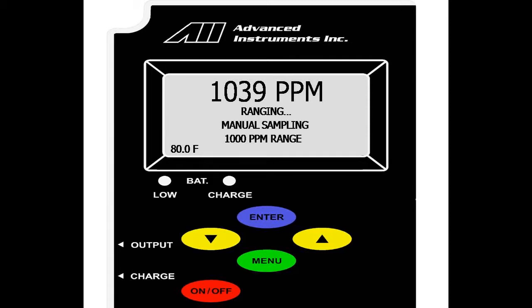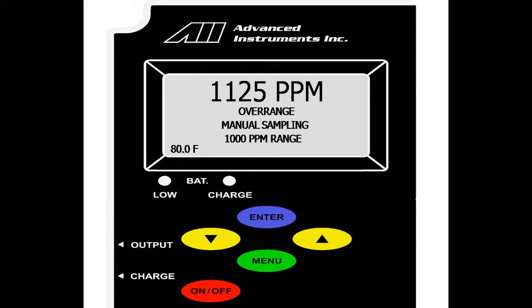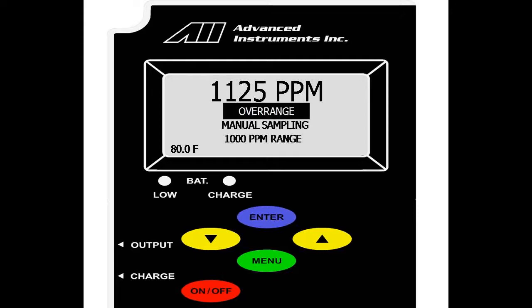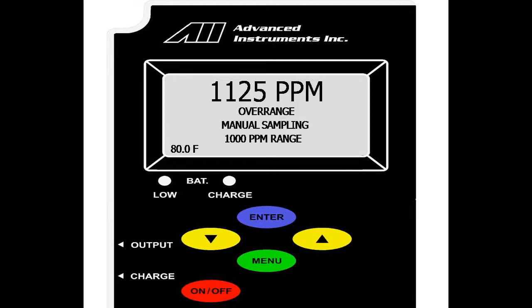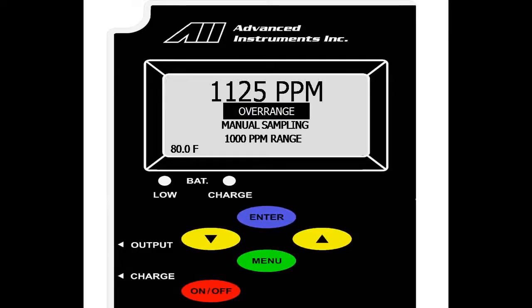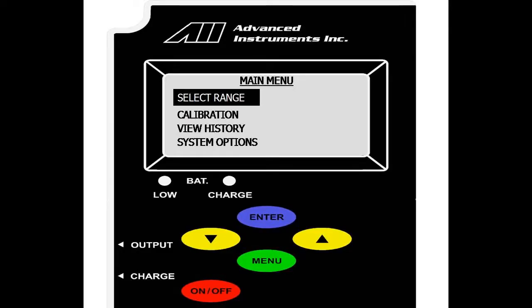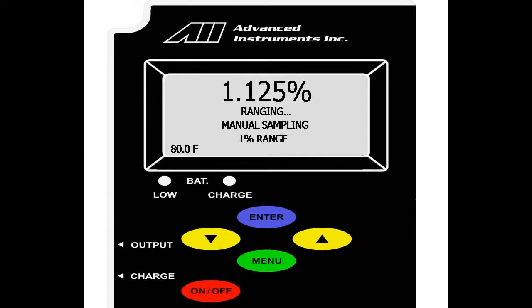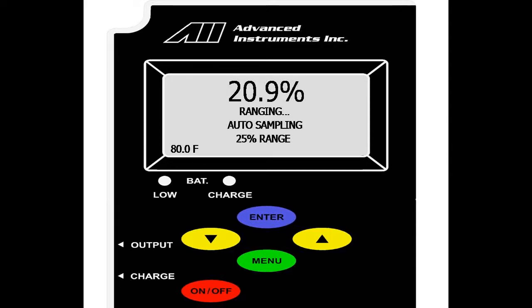As you can now see on the screen, it is manual sampling mode at 1,000 parts per million. Currently, the analyzer is reading 1,125 and over ranging. This indicates that the sensor is above the given range and the range will read 12.5% higher than the limit of 1,000. We go back to menu, enter on select range, go back to auto ranging and the analyzer will auto range back to the 25% range. You can manually fix your range through the select range option and manually fix your 0 to 1 volt as well.